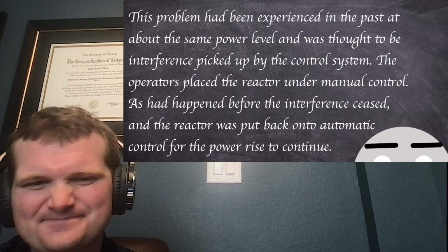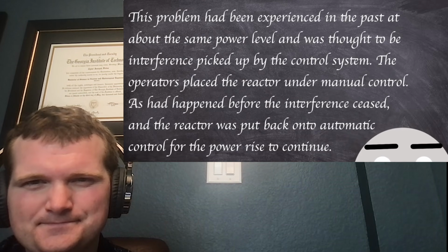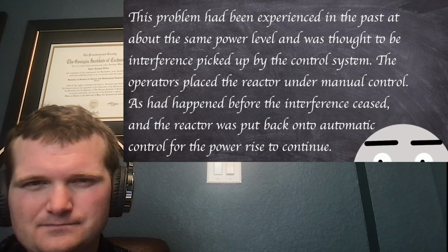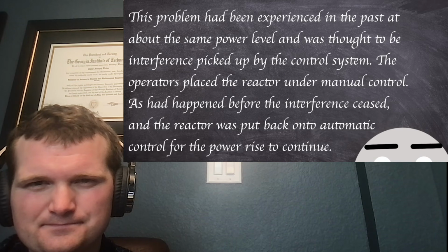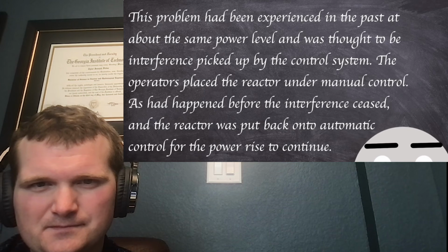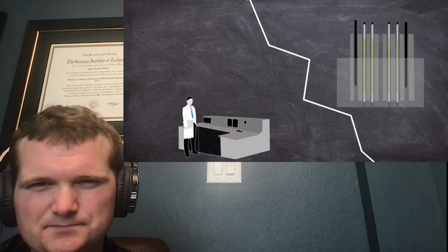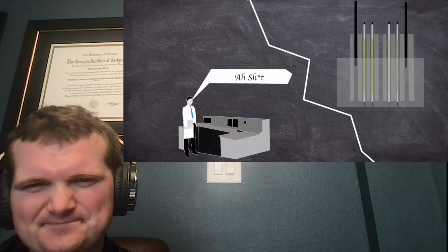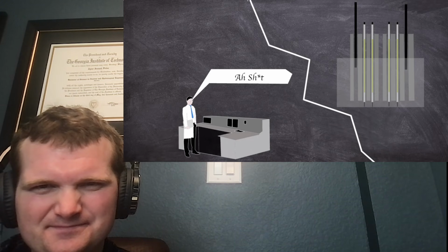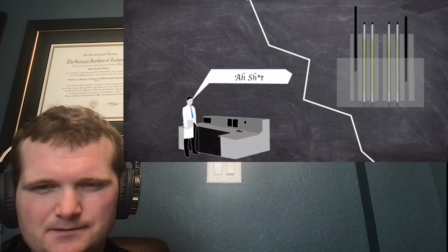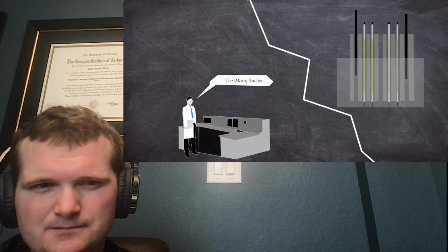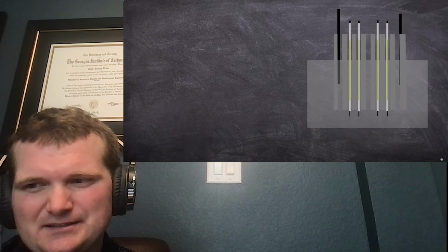I've never done that. This problem had been experienced in the past at about the same power level and was thought to be interference picked up by the control system. The operators placed the reactor under manual control. As had happened before, the interference ceased and the reactor was put back onto automatic control for the power rise to continue. Just after 3 p.m., a staff member in charge of the operation saw that the control rods appeared to be withdrawn further than normal for this power level. Both the shim and regulating rods were approximately 9 inches withdrawn. Usually at this time the rods would be at around 6 inches. And that's the other reason.